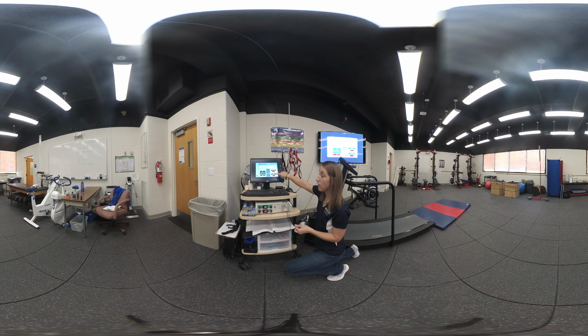This is specifically the voltage that it's pulling in to assess the oxygen and the carbon dioxide content. What's important on the screen up here is that these little dials are within the green region. We can see that they're both within the green region and they're steady and they're not moving. Once we're at that point, we can go ahead and select start.